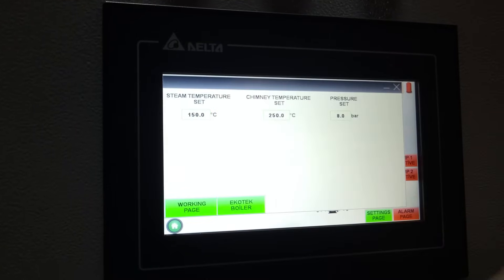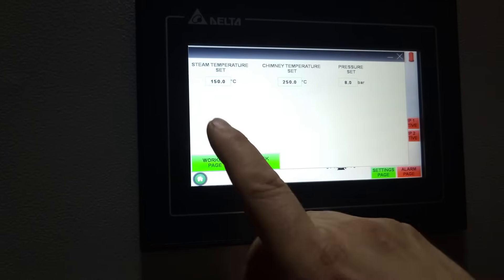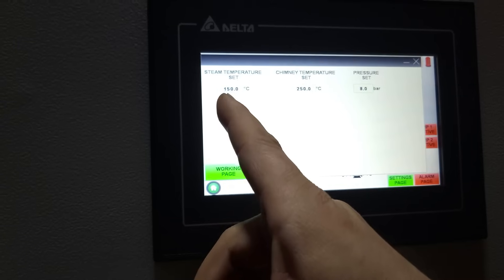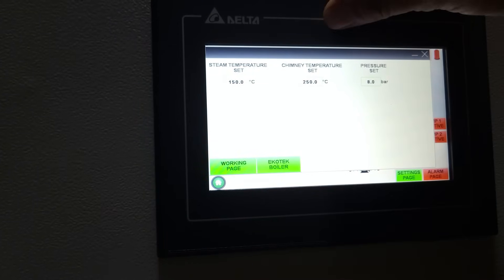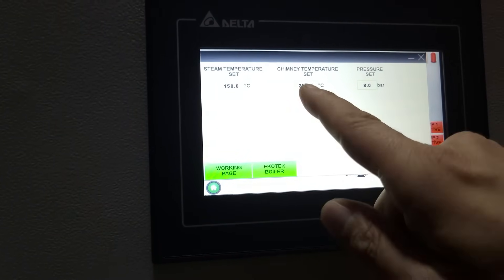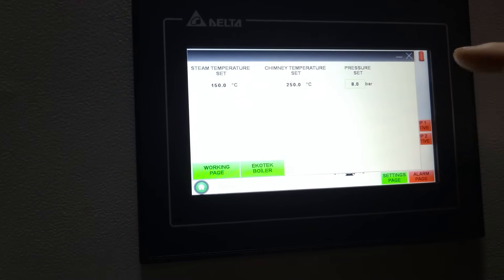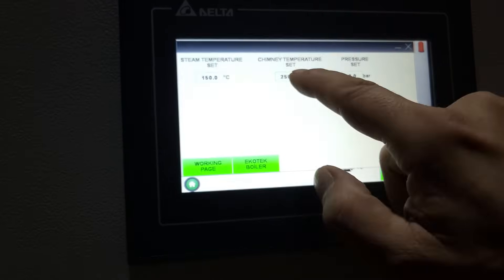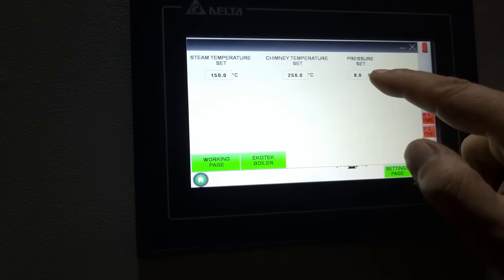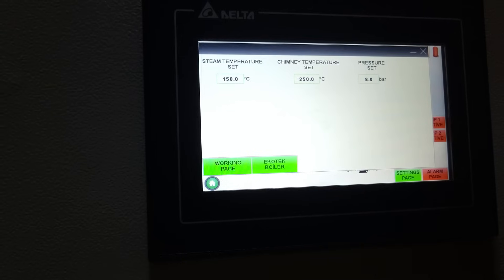Now we are in. On this window you can change the settings: the steam temperature is currently set to 150°, the chimney temperature is set to 250°, and the pressure set point is eight bars. By clicking on the fields here, you can change the desired value.